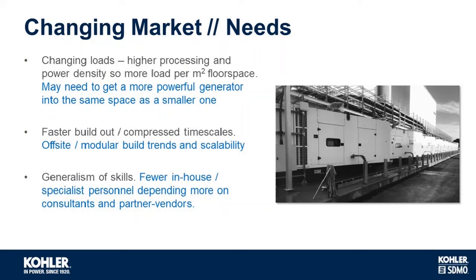So what's changing in the market and what are the needs? Well, power density of IT is certainly increasing, which puts pressure on the IT space and pushes the need for more powerful generators. Also, the faster the construction, the lower the build costs through compressed timescales. Manufacturing packaged generators off-site using modular, repeatable designs, which can be easily scaled up into multi-megawatt installations, also reduces cost and operational complexity when the data center is live. And the generalism of skills means that clients tend to have fewer in-house specialist personnel, which drives a higher dependence on consultants and partner vendors to provide that specialist knowledge.